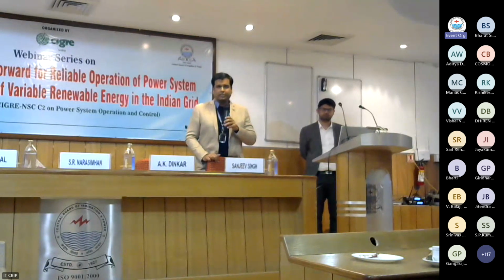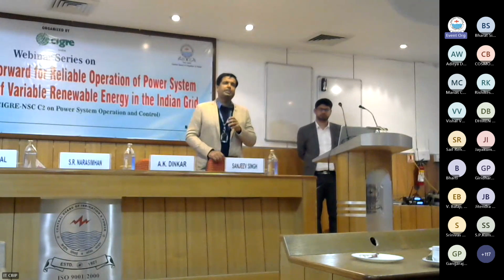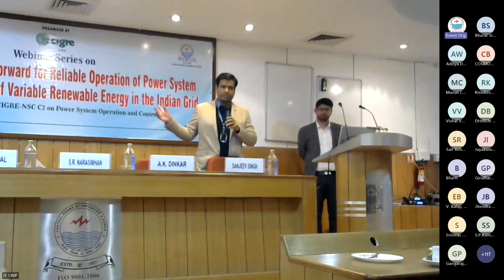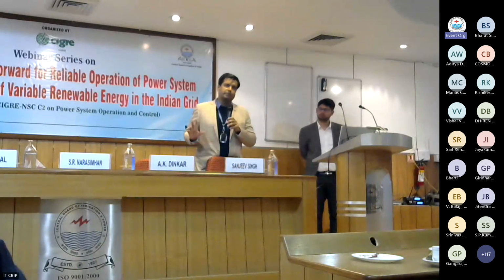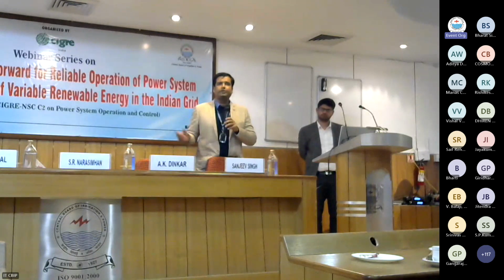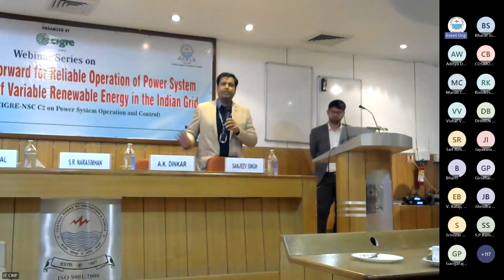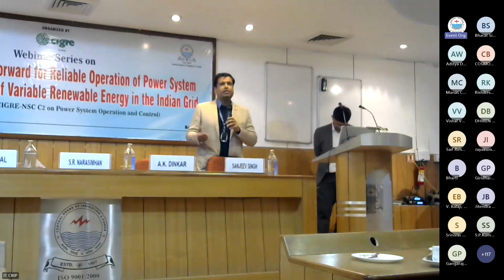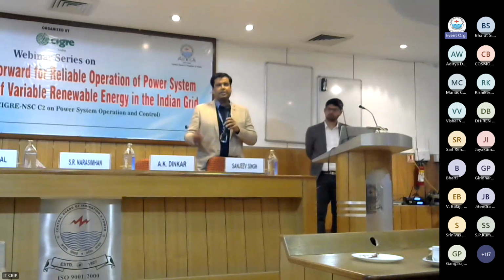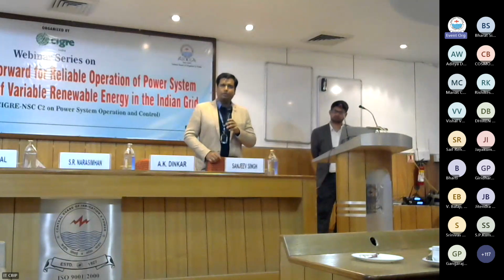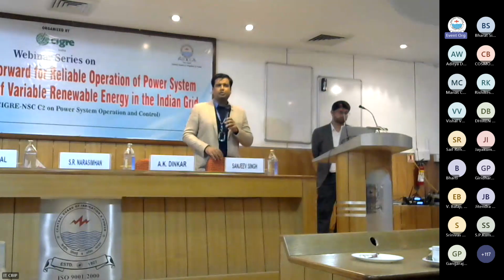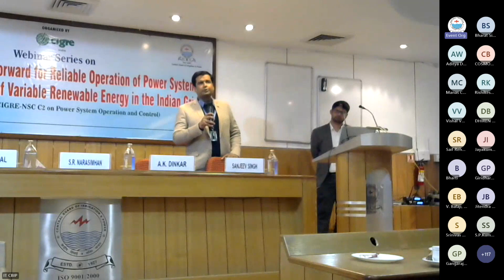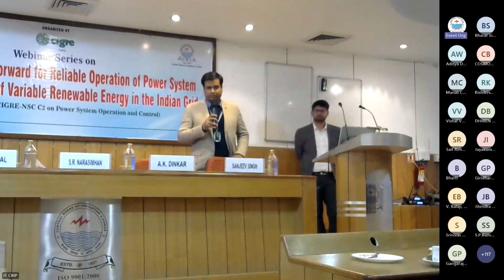But yes, standards are not only required for the inverter duty transformers. As we mention in the slides also, for a complete plant, all the equipment should be standardized so that they are able to display the desired behavior during extreme events like LVRT, HVRT. Other than that, what happens within the plant, the inverter duty transformers, those are at very low levels, 2.5 MVA, 11 MVA, like that. So we do not go into those details of the plant, being a grid controller.